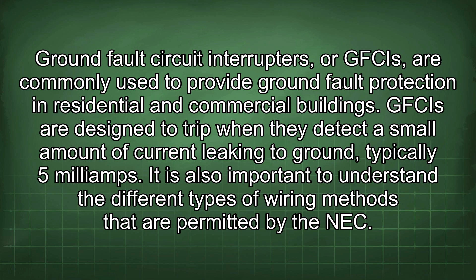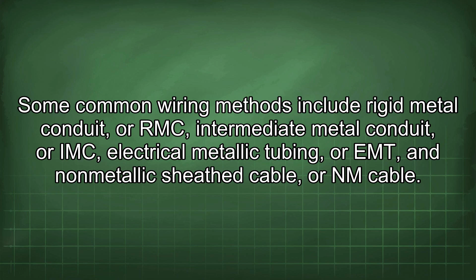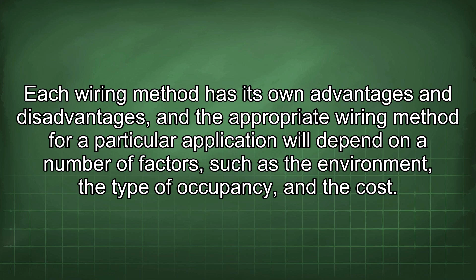It is also important to understand the different wiring methods permitted by the NEC. Common methods include rigid metal conduit (RMC), intermediate metal conduit (IMC), electrical metallic tubing (EMT), and non-metallic sheathed cable (NM cable). Each has its own advantages and disadvantages, and the appropriate method depends on factors such as the environment, type of occupancy, and cost.